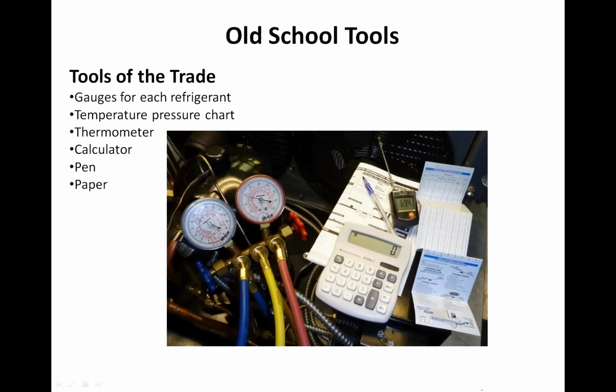The old school tools of the trade were gauges for each refrigerant. If you remember being in this industry for a while, we had an R12 set of gauges, we had an R22 set of gauges. Now we have an R410A set of gauges. You required 3 sets of gauges. You had a pressure temperature chart you had to carry in your pocket. You had a thermometer that you carried, some kind of a high accuracy thermometer, superheat thermometer, maybe a calculator, pen and a paper to calculate the superheat and the subcooling.